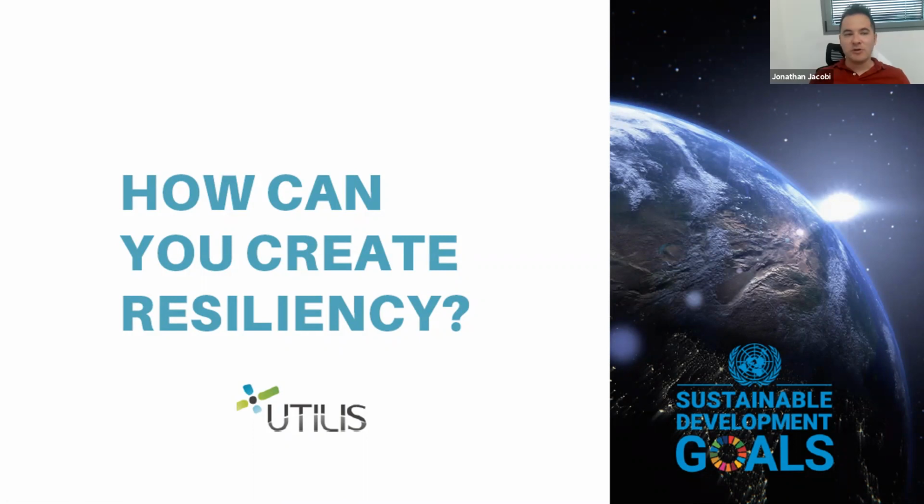It hasn't. I'll tell you from what I know. I've also been a few times with teams out in the field investigating. Because the groundwater is so high in Bangkok specifically, the majority of the pipes are in very shallow ground, no more than 1 meter deep. The service pipes could be anywhere between 30 and 80 centimeters, and the main pipes maybe tops 1.5 meters. So they try anyway to keep it as close to the surface as possible. And as long as it's mixing with the ground, it doesn't matter.